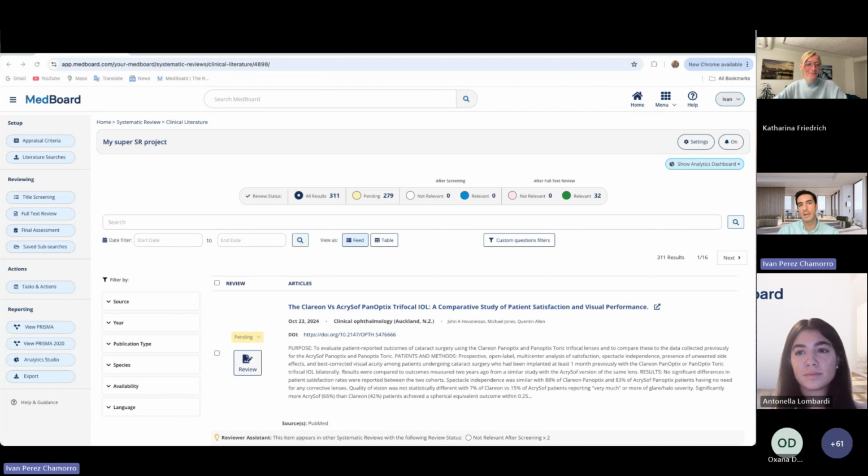Yeah. Absolutely. And from our side, we share the same message. As long as you can justify and add a rationale, no one can force you to review 10,000 articles because one database gives you 10,000 articles and PubMed is giving you 100 for the same query. So obviously it has to be justified as well why you include that specific database. That's always requested by reviewers and auditors, why that specific database was considered to be included.